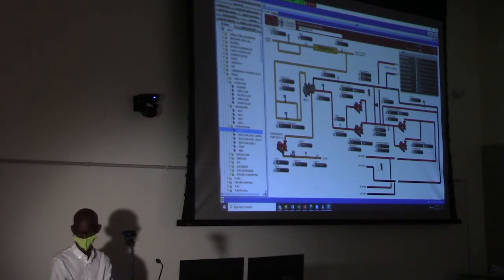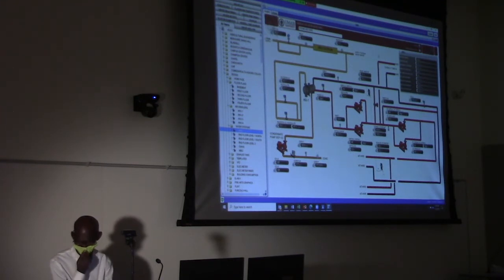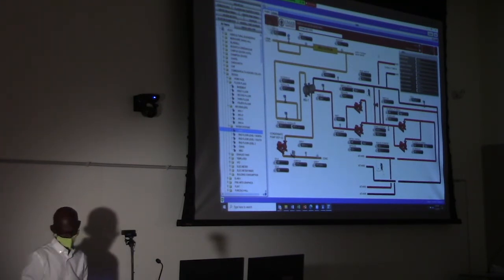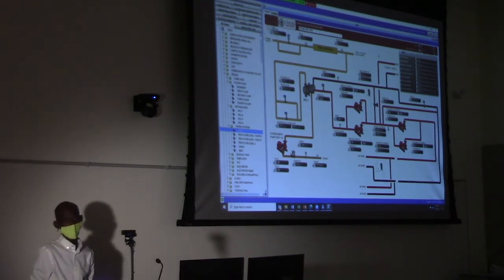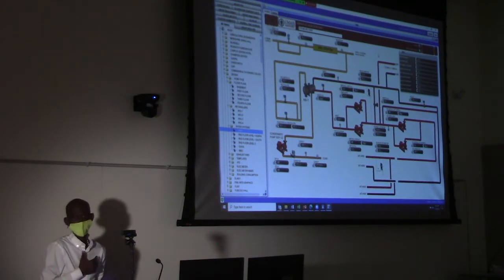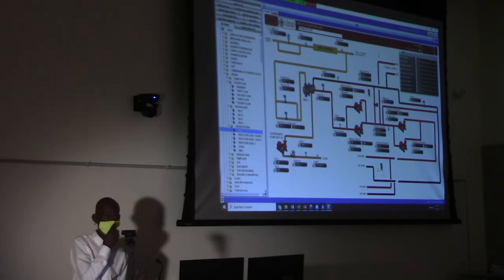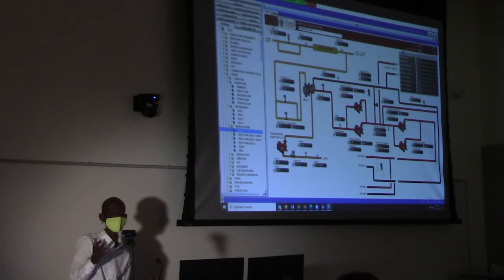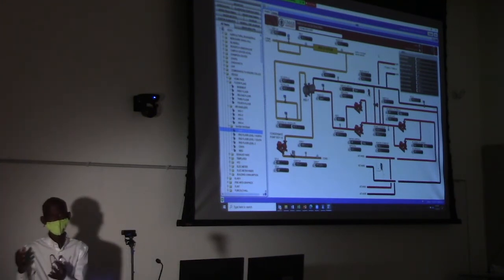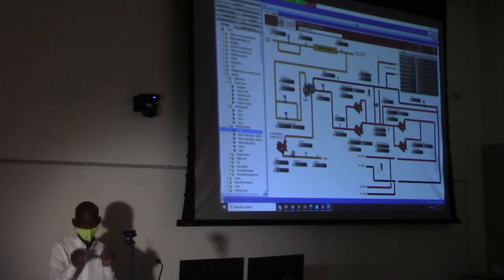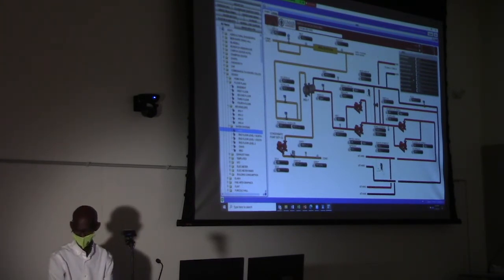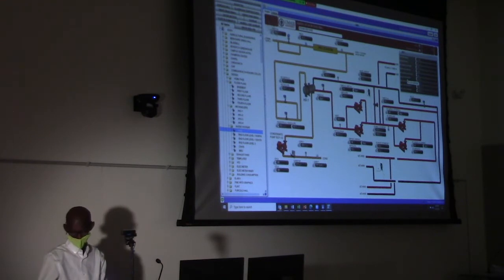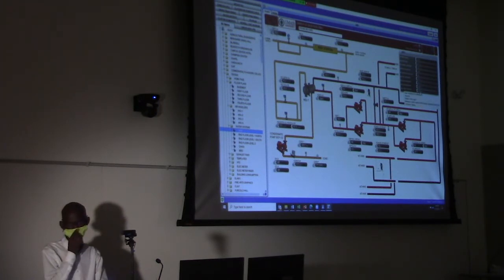This is the screen that shows us the lead and lag. Another thing too is for the hot water temperature. If it's 60 degrees outside, you don't want to supply 180 degrees. It's too hot. But if it's 0 degrees outside, you want to heat your building quickly. You want to give it a higher temperature. So here's a temperature reset. It tells us low set points, high set points. If it's 15 degrees outside or below, you have to provide 180 degrees Fahrenheit hot water to the building.